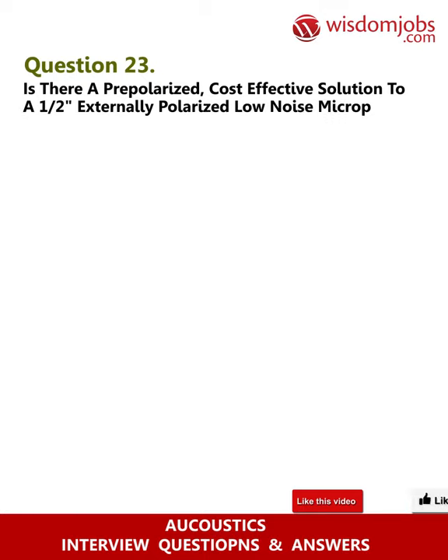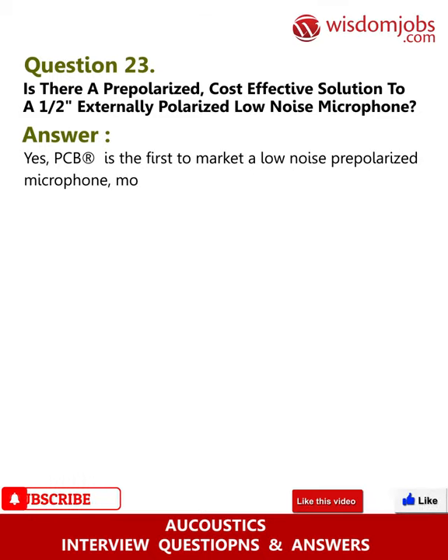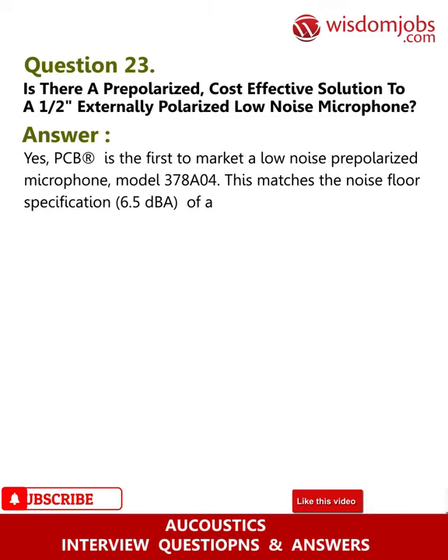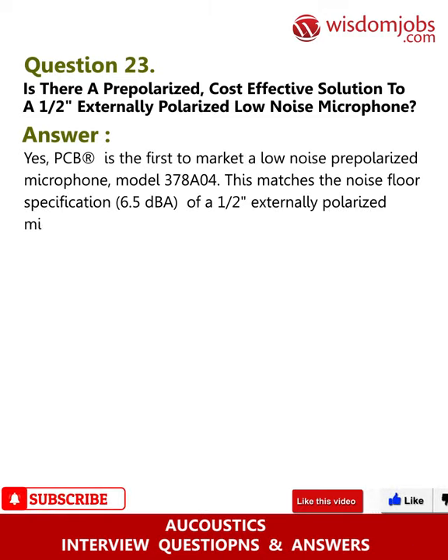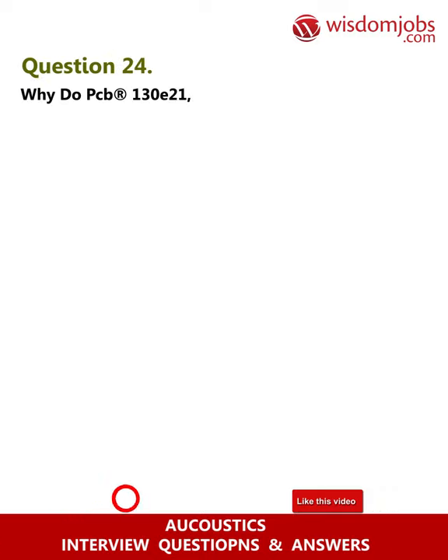Question 23: Is there a pre-polarized cost-effective solution to a half-inch externally polarized low noise microphone? Answer: Yes, PCB is the first to market a low noise pre-polarized microphone, model 378A04. This matches the noise floor specification of 6.5 dB(A) of a half-inch externally polarized microphone.